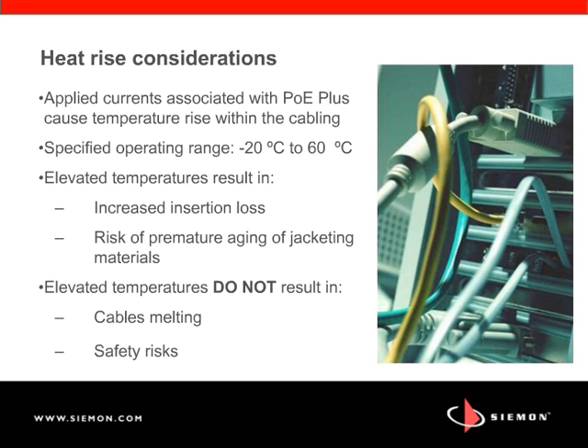And we also need to take into consideration the mechanical performance of the cabling. What operating temperature are the cables specified for? If we exceed the operating temperature, we do risk the potential that the jacket materials will age prematurely. That means they may become harder or brittle sooner than they were designed to. Now, I want to emphasize that the types of temperatures we're talking about are about 120 to 140 degrees Fahrenheit in the worst case environment.